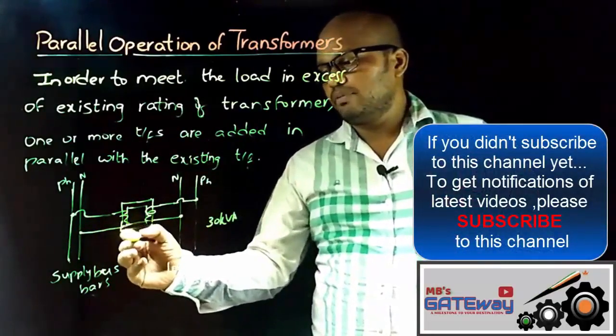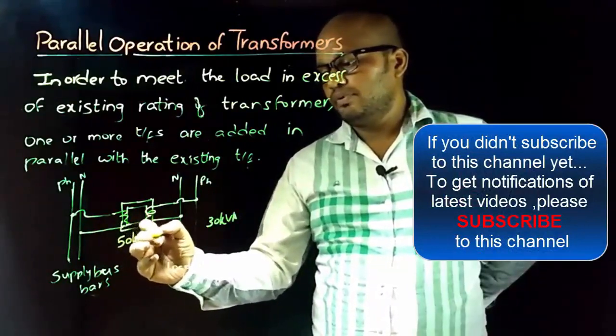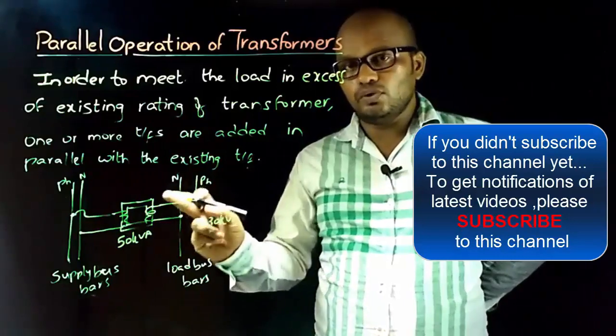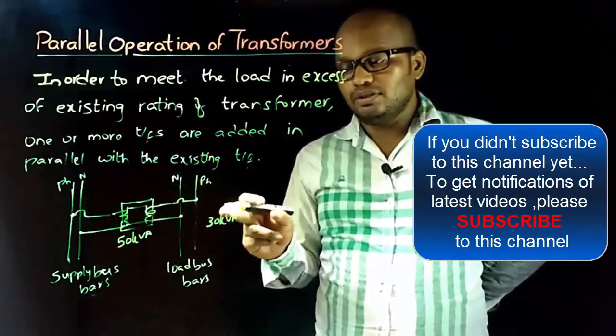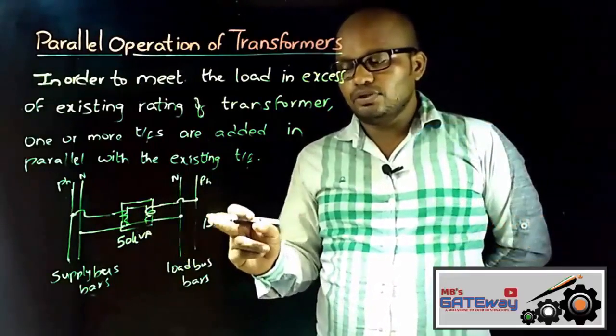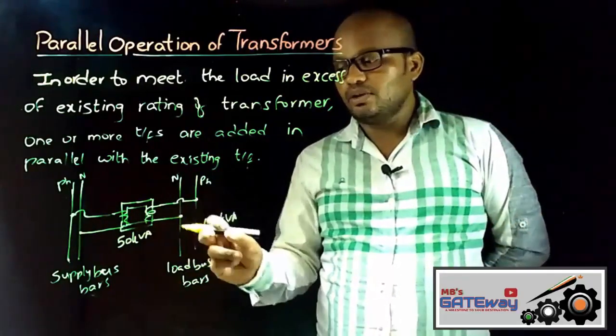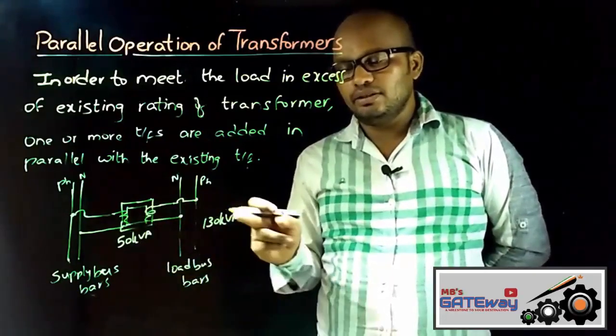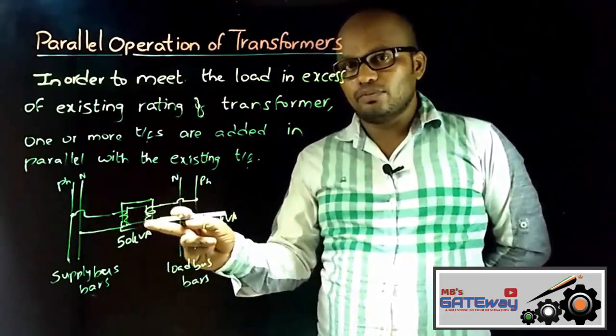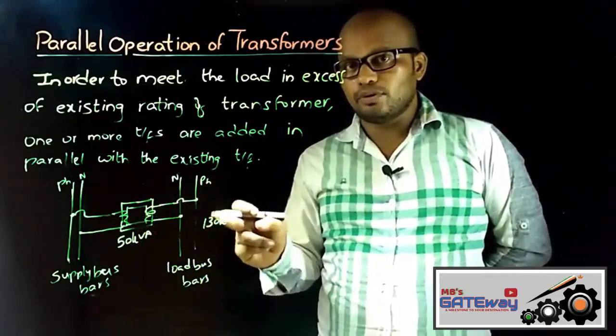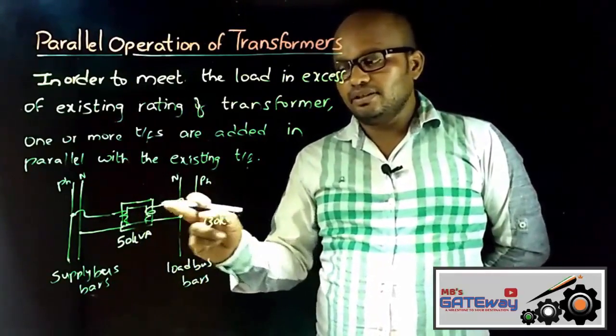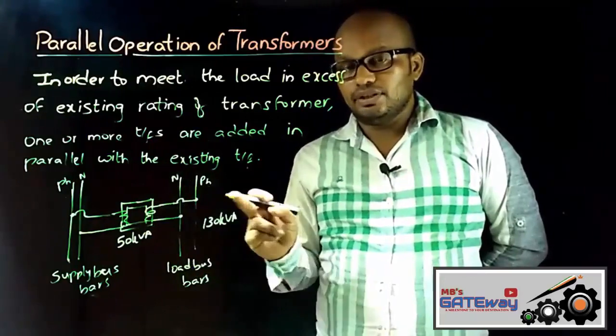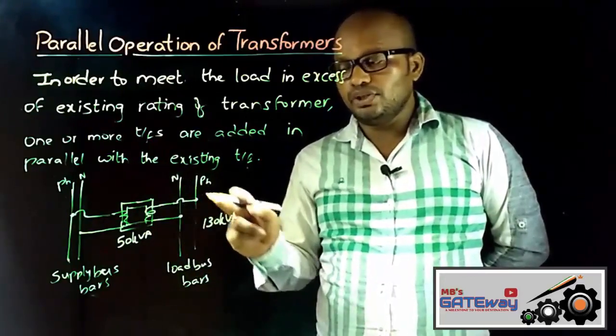Suppose the load is 30 kVA and the transformer rating is 50 kVA. Here the transformer can supply the required power to the load without overheating, because the load requirement is less than the transformer rating. Suppose the load is now 130 kVA. As the transformer rating is less than the load requirement, the transformer can't supply the required power, and if it is left like this, then this transformer will get overheated. Therefore, to supply the required power to the load, what must we do?